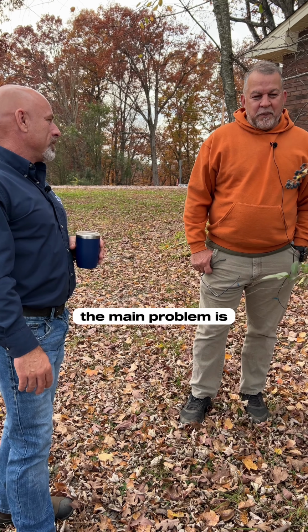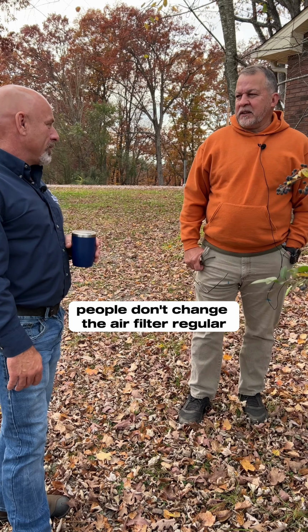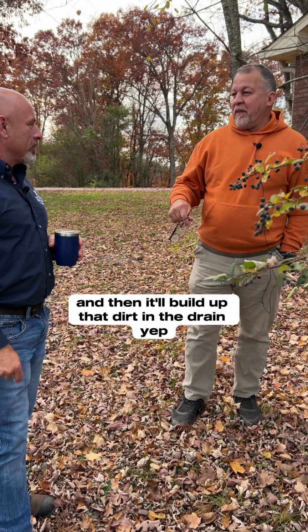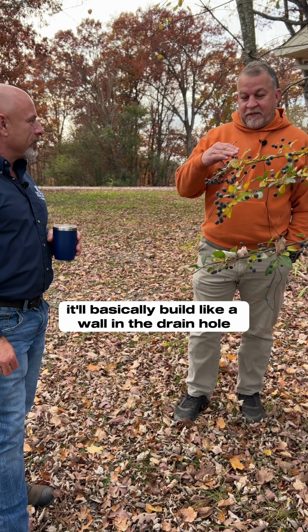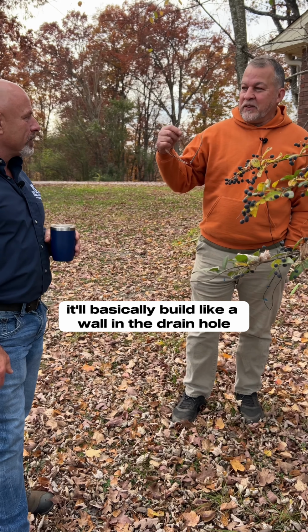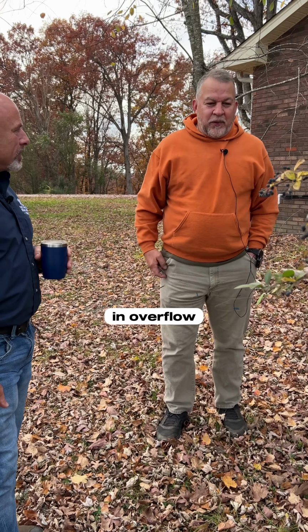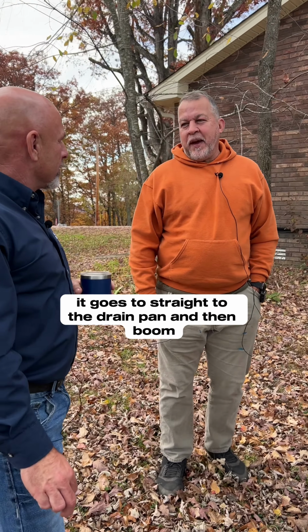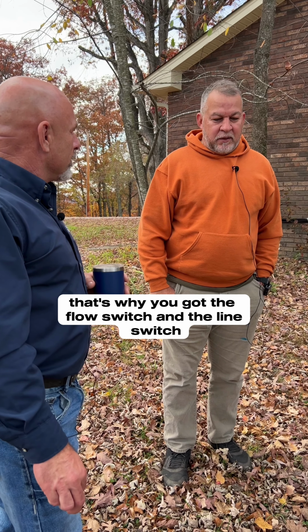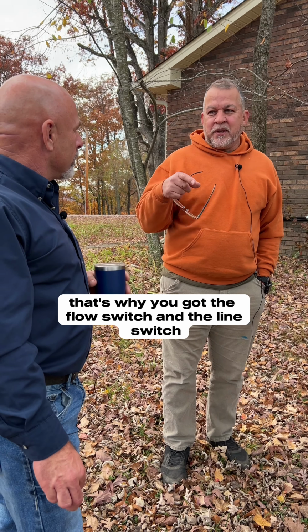The main problem is people don't change the air filter regularly, and it builds up dirt in the drain, basically like a wall in the drain hole, and it overflows straight to the drain pan, then boom, to the ceiling. But that's why you got the flow switch and the line switch, you could put that also in the system.